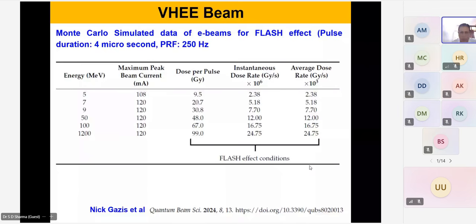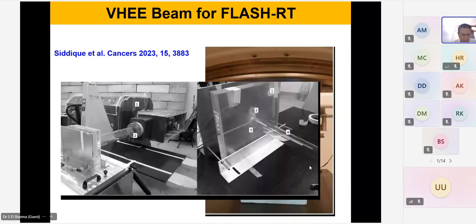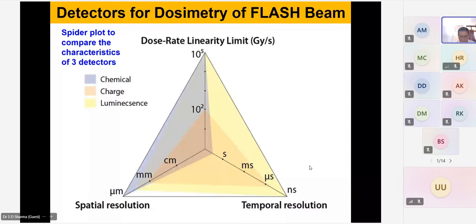So this is a photograph of one of the systems. You can see the dosimetry work is going on. Now, if we talk about the dosimetry of the system from the physics point of view, because of the very high dose rate, our existing ion chambers may not work. They will have the problem of charge recombination. So you can see the spider plot.